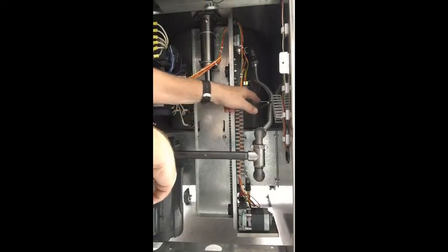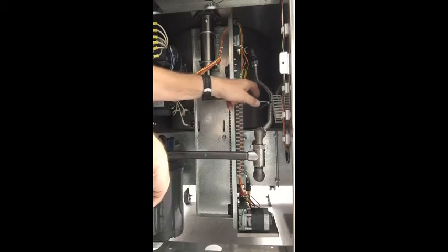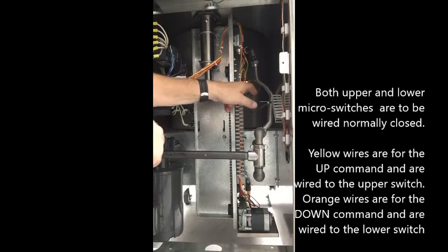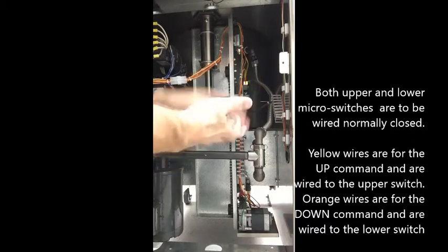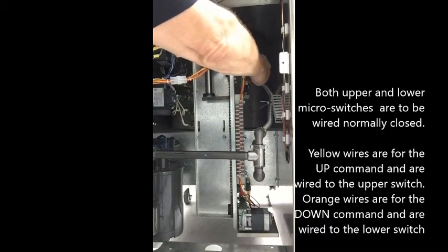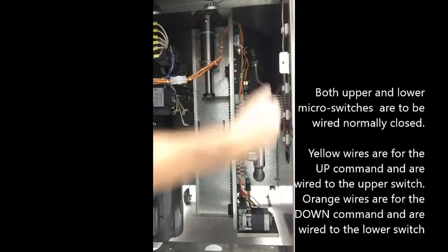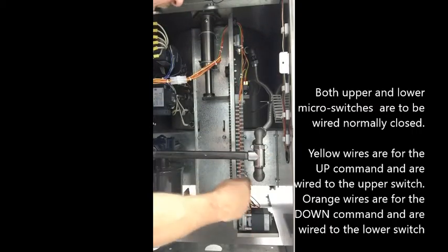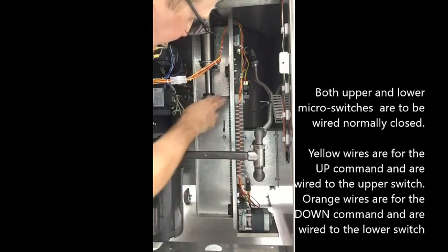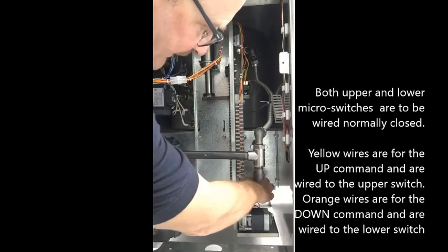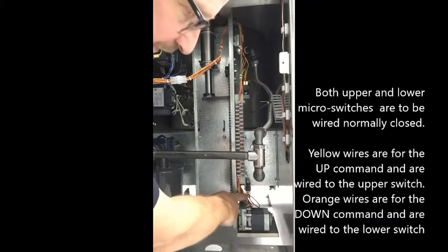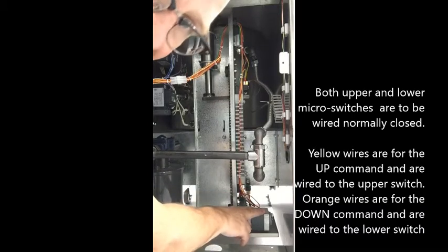When it comes up to the top, it'll make this micro switch. The micro switch is wired normally closed, so it'll break the circuit on these two yellow wires. Yellow is up. It'll break this circuit and kill power to the motor. When it goes down, this same key makes this micro switch down here that has two orange wires on it, breaking power to the motor going down.